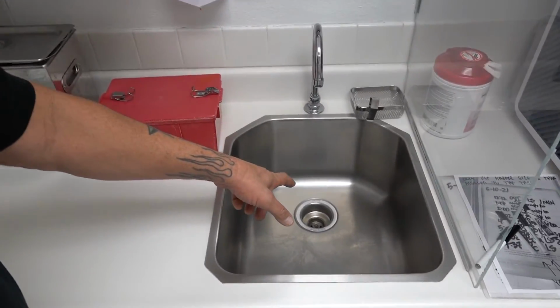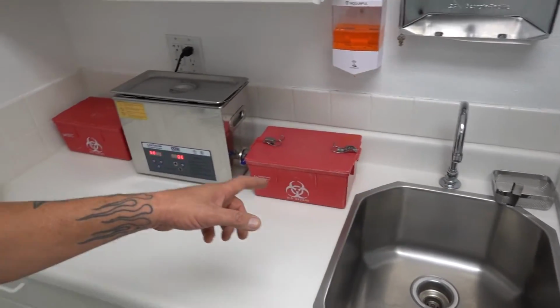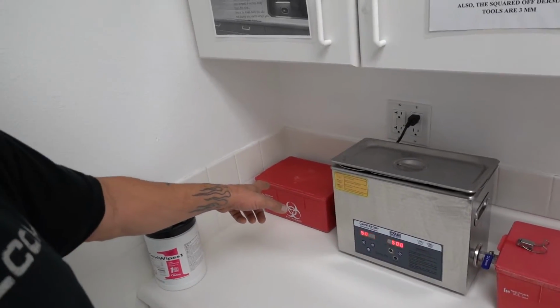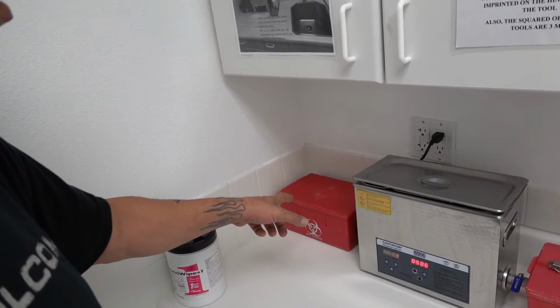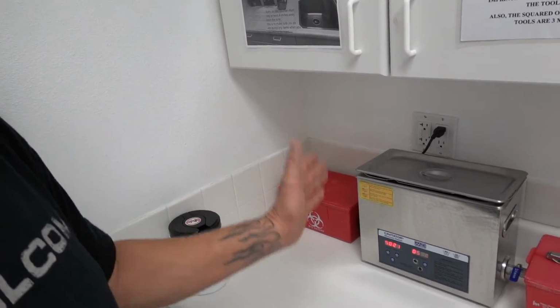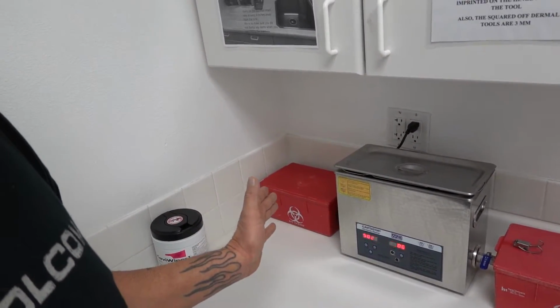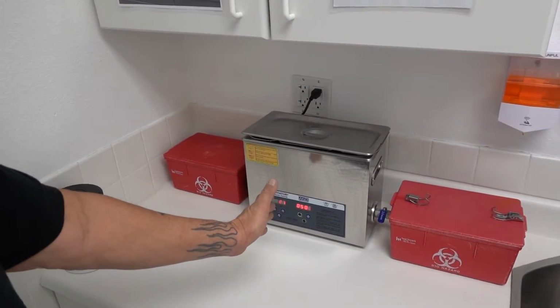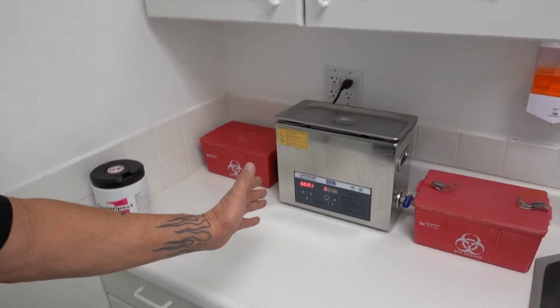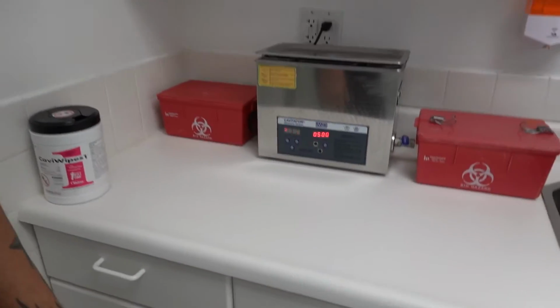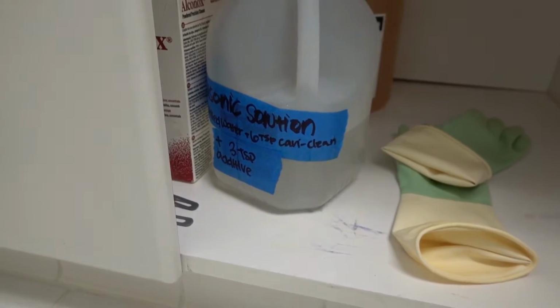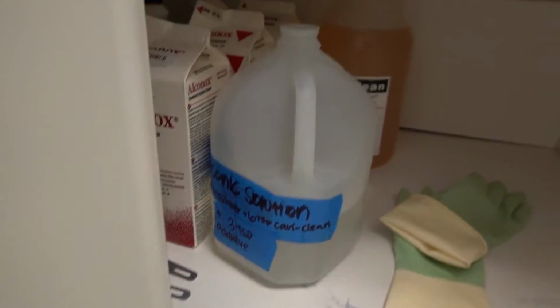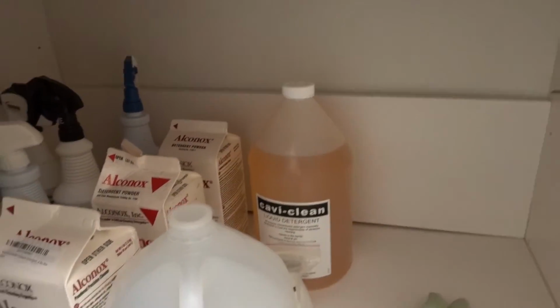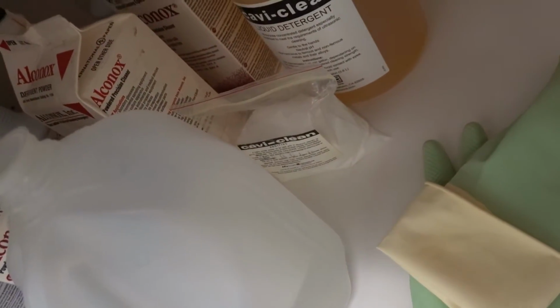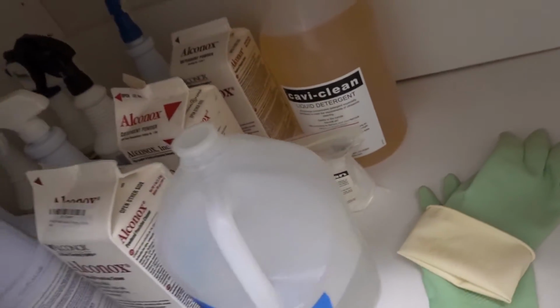We then scrub our instruments in this sink. We then soak our instruments for 20 minutes inside Metricide. In between each one of these steps, we rinse our instruments. We then put our instruments in the ultrasonic. We only use the cleaner that is recommended by the manufacturer for the ultrasonic, which in this case is CaviClean. There's also a powder right there that's an additive for CaviClean.